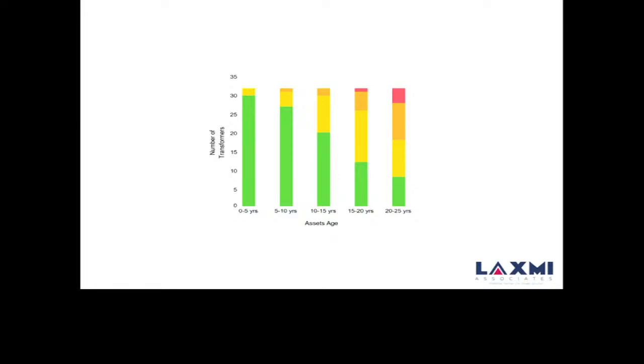The message given by health index is that all the transformers in your system will not perform the same way. Each will have its own performance depending on loading condition, quality, design, maintenance—everything considered, this can vary.